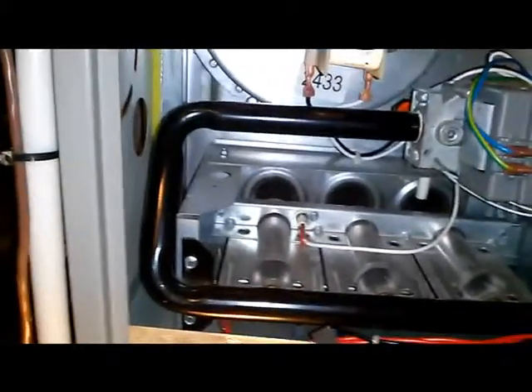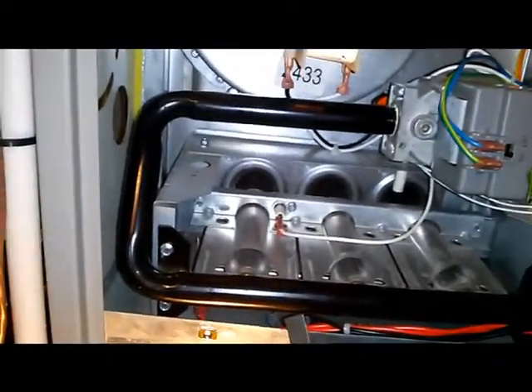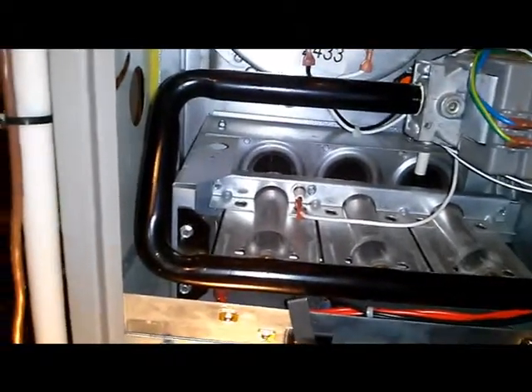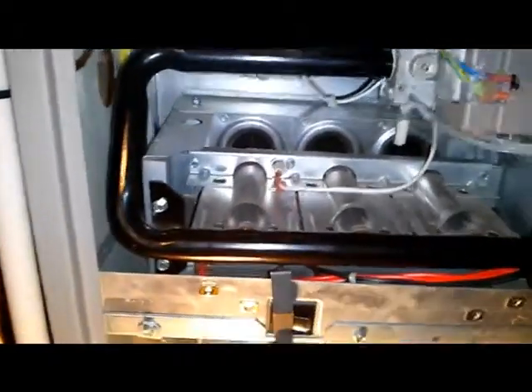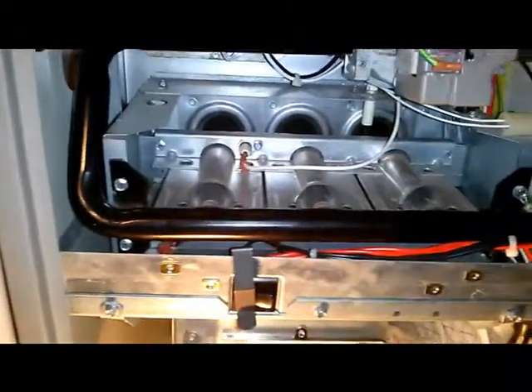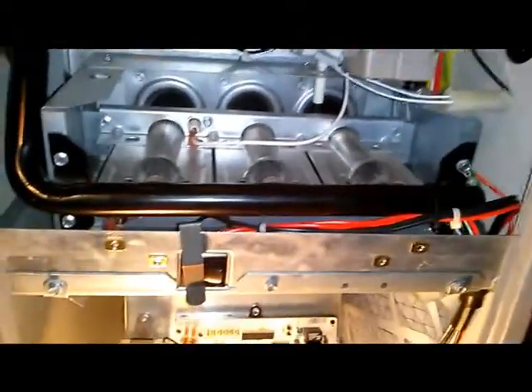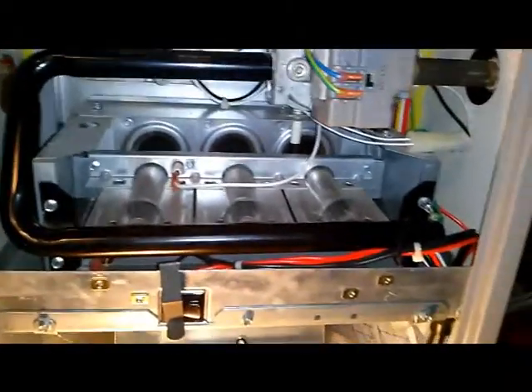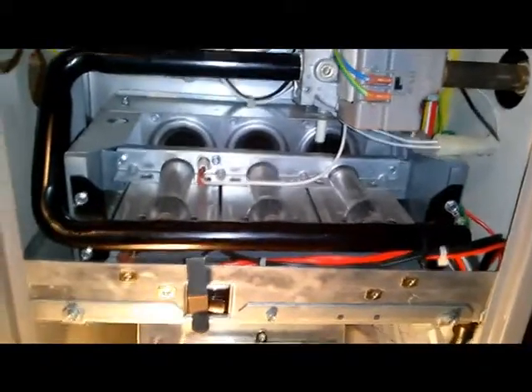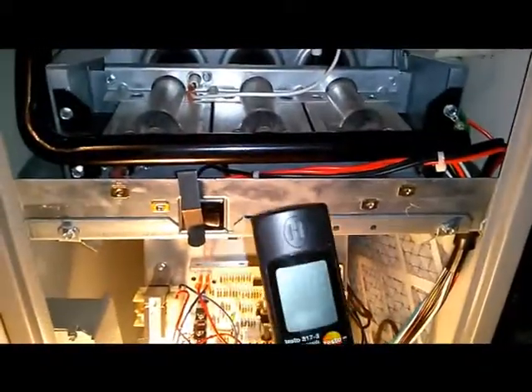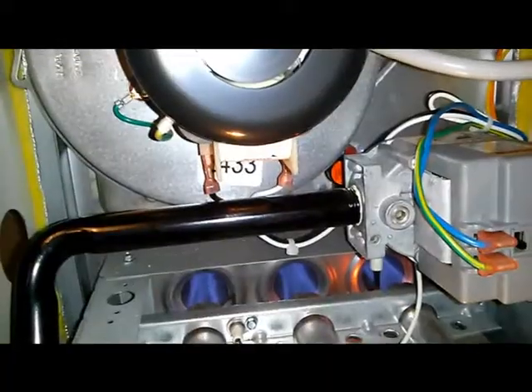So what I'm going to do now is my final startup, just to make sure everything's working good before I say this furnace is fine. I'm also going to do a carbon monoxide test, because we want to make sure there's nothing leaking from the furnace, so I'm going to stick this above where the plenum is.